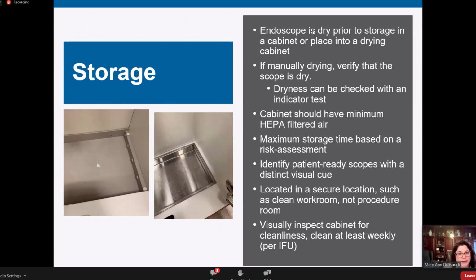And there are different drying indicator tests that are available on the market. So you'd set what it is that you're going to use and at what interval, and check your different kinds of scopes, right? I'm not saying every scope every time for this, but it might be monthly or weekly or quarterly that you do a dryness verification test on your different types of endoscopes to show your process is still in control. At minimum, if you don't have a drying cabinet, you should have HEPA filtered air circulating within the cabinet. So we shouldn't be using ones that don't have any ventilation or any HEPA filtered air going through them.